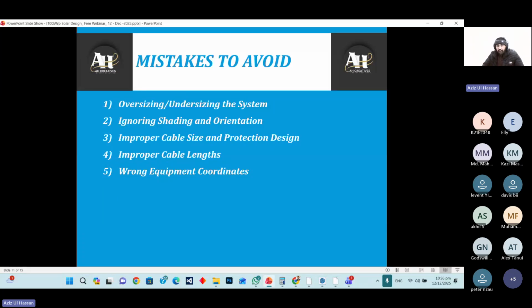Improper cable sizing and protection design: proper cable sizing and protection design is very important. When we are not doing that properly, it will cause harm to the lives of the humans working in that area, and it will also cost money. Improper cable length: when we are calculating the length and the voltage drop and we do not do it properly, it will cause more cable losses in the form of power, and it will decrease the performance and the energy output of the solar systems.